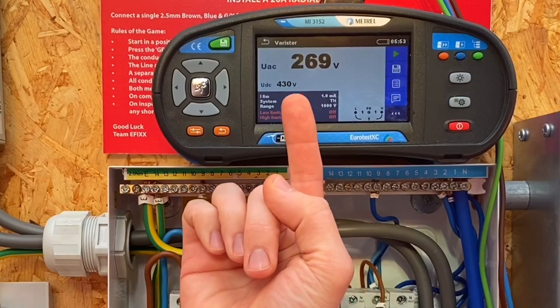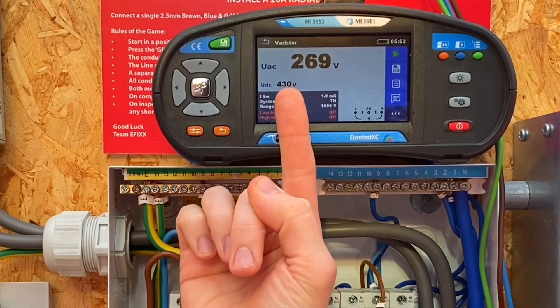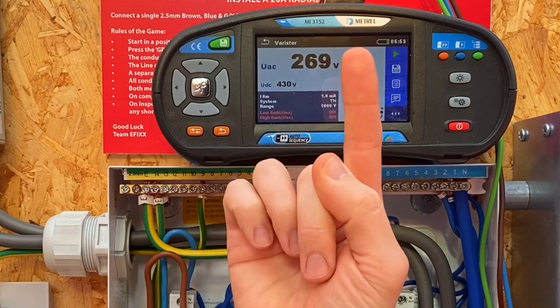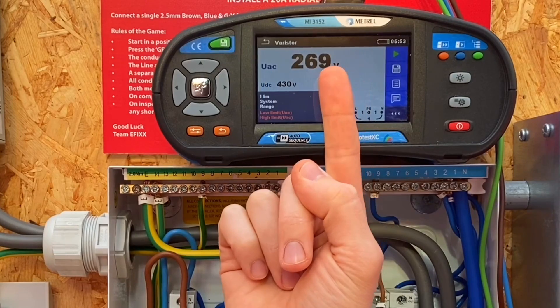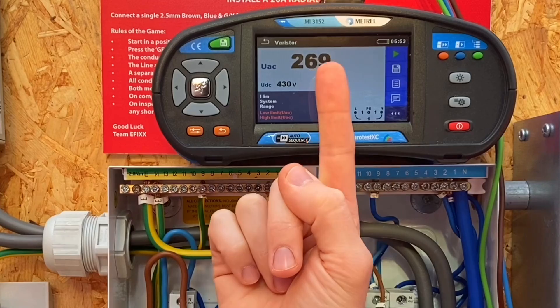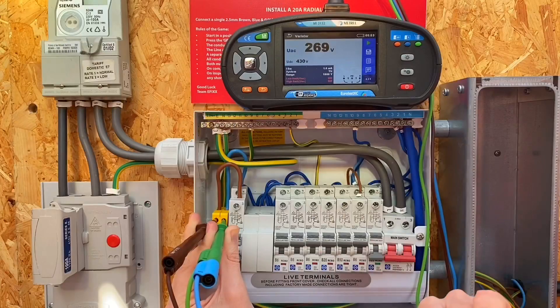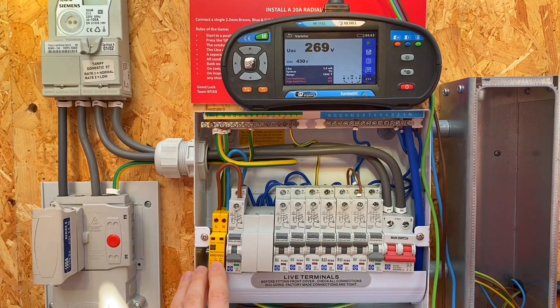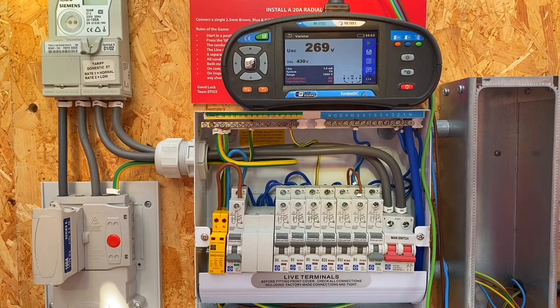That's the point at which the varistor starts to conduct electricity and suppress the surge. You can see two interesting values. First we've got UDC - that's the DC voltage the tester has applied: 430 volts. That has been calculated to give us a UAC or AC voltage of 269 volts. That's the value we're interested in, because that is the voltage at which this surge protection device starts to allow more than one milliamp to trickle through the varistor. We were expecting 275 volts and we've come out with a value very close to that - 269 volts - so we know the varistor is working correctly.